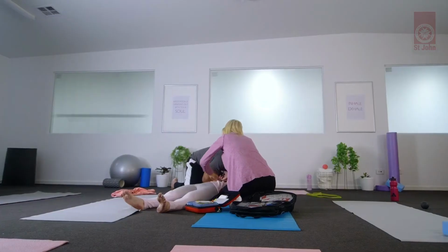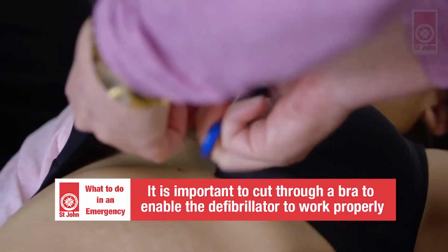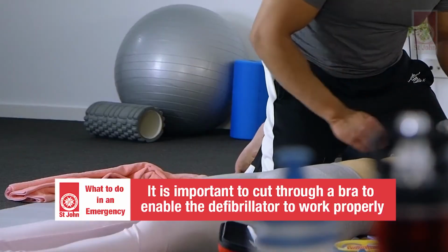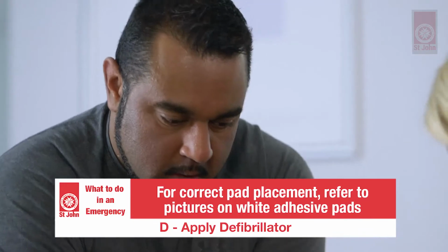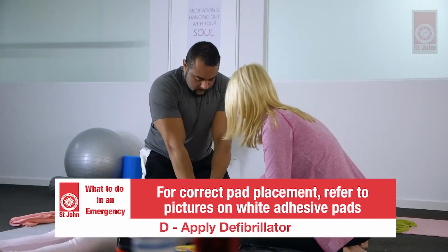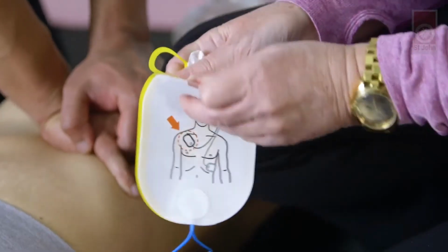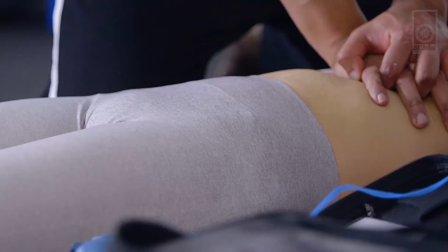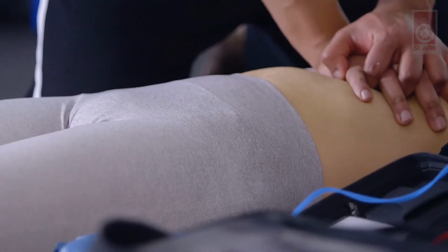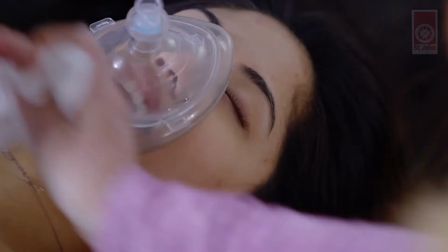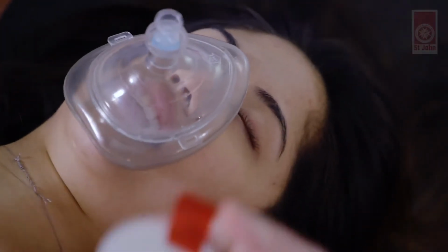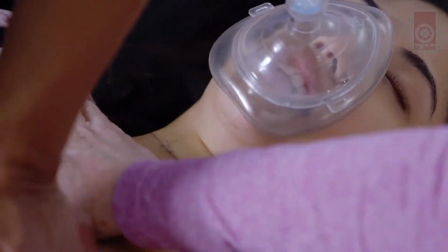When the patient's chest is bare, remove the protective cover and take out the white adhesive pads. Look carefully at the pictures on the white adhesive pad. Peel one pad from the yellow plastic liner. Place the pad exactly as shown in the picture. Wipe away any sweat. Their skin should be dry. Press firmly to the patient's bare skin.